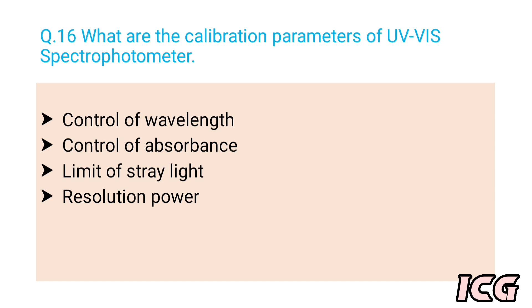The next question is: what are the calibration parameters of UV-Visible spectrophotometer? There are four parameters: the first is control of wavelength, the second is control of absorbance, the third is limit of stray light, and the last one is resolution power.